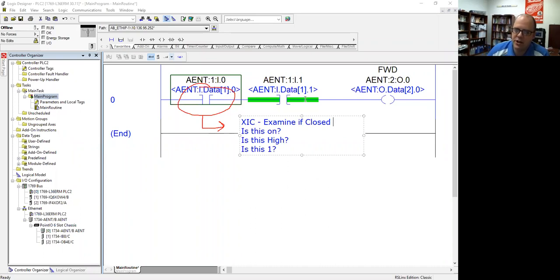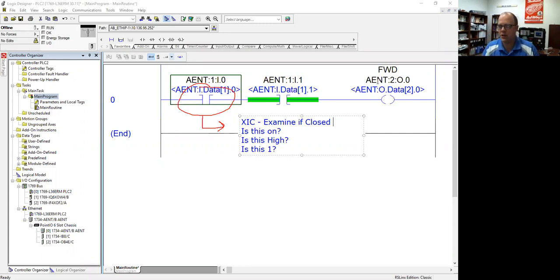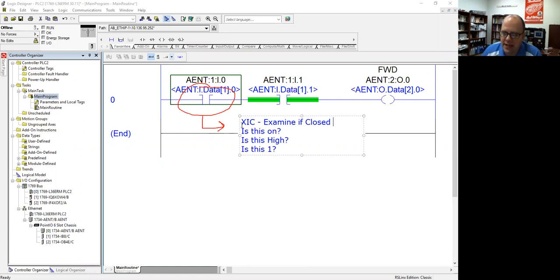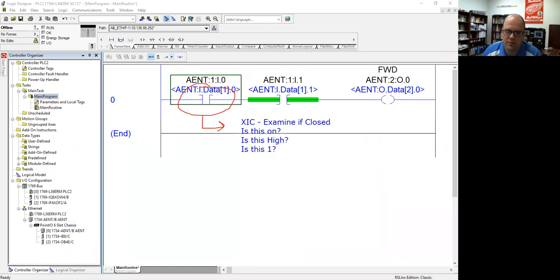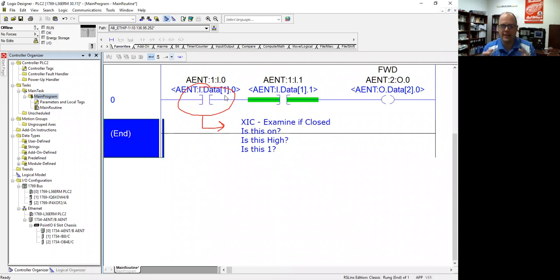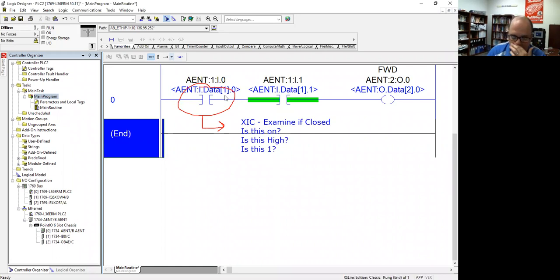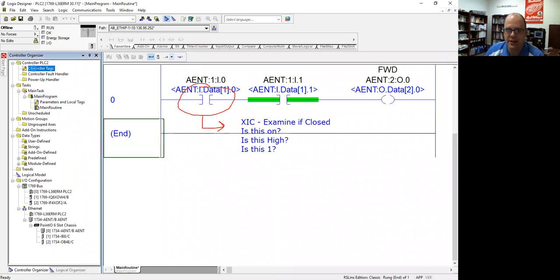If it is, it's going to turn green. It's true. So if it's a one, it will return green and say yes. And if we can bundle a bunch of these questions together, this will then turn on this output. That's the examine if closed or if on. Whenever you see it, it's not a normally open contact. Get out of that habit. It is examine if on or examine if closed, meaning contact closed. And if you see that, start asking the question, is this on? Is this high? Is this a one?